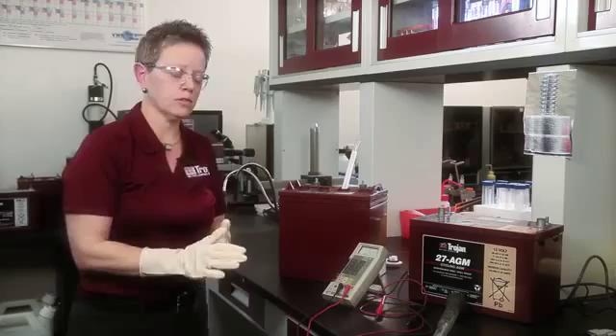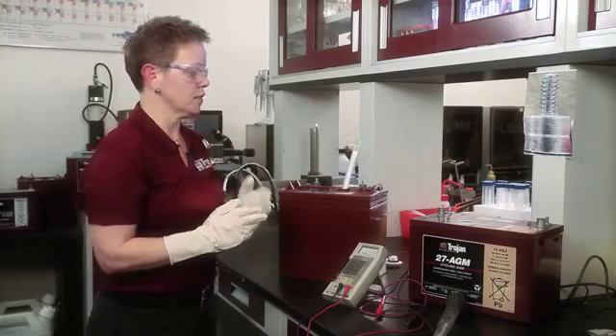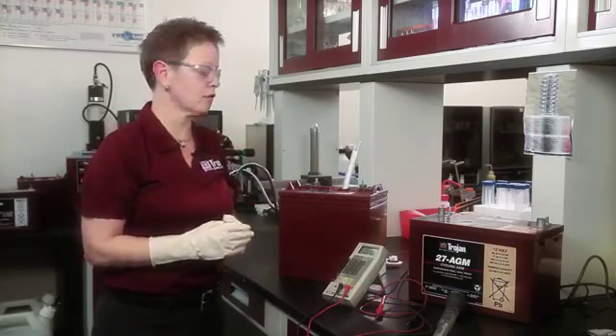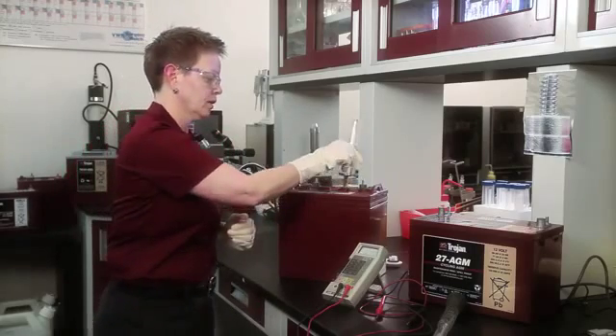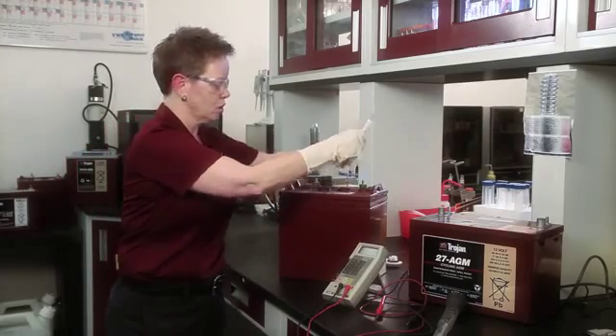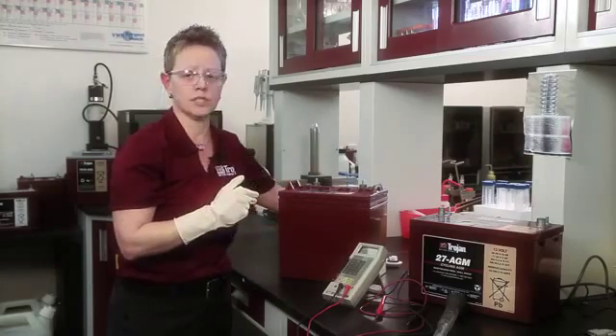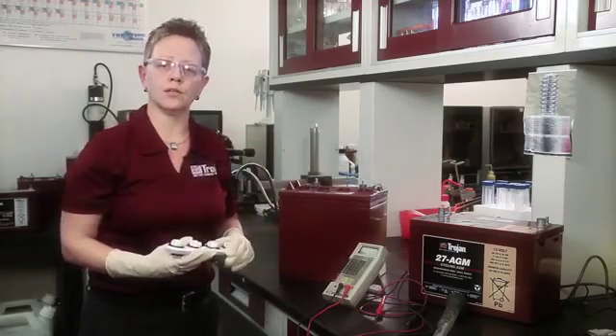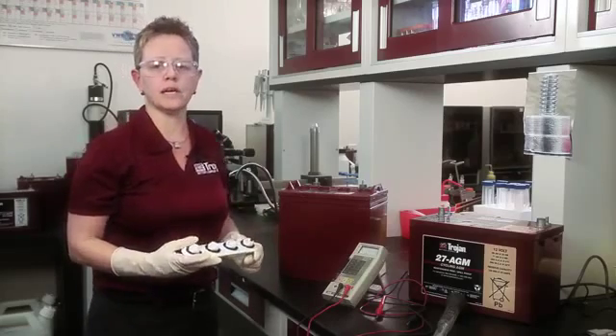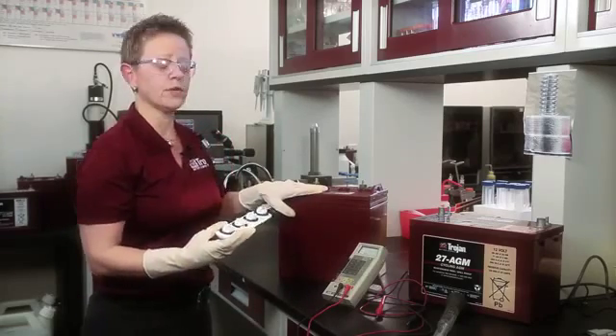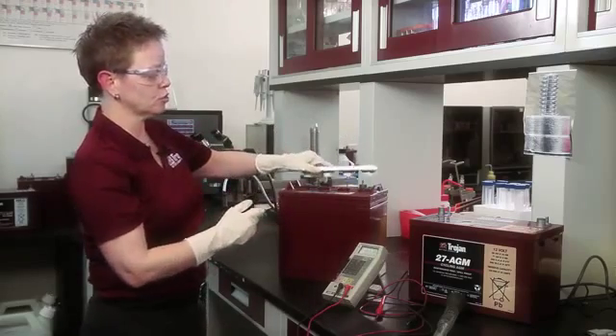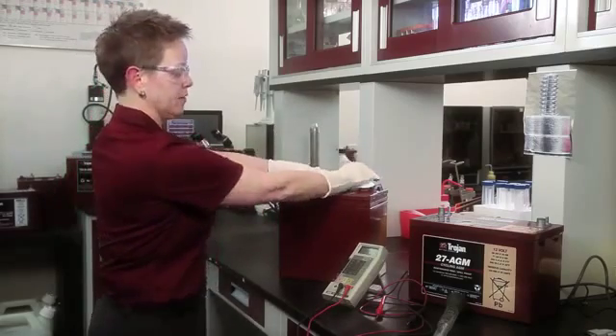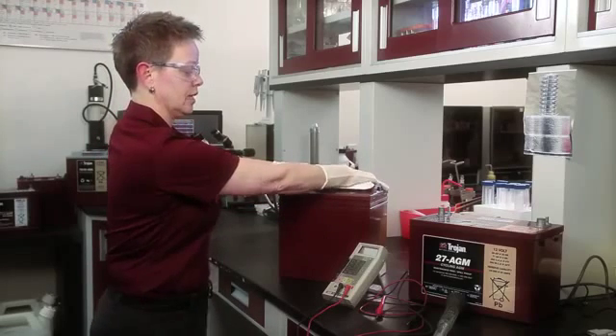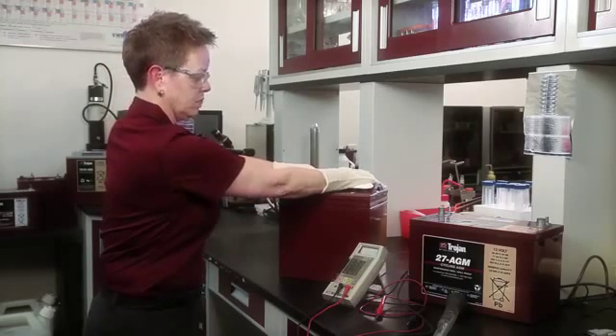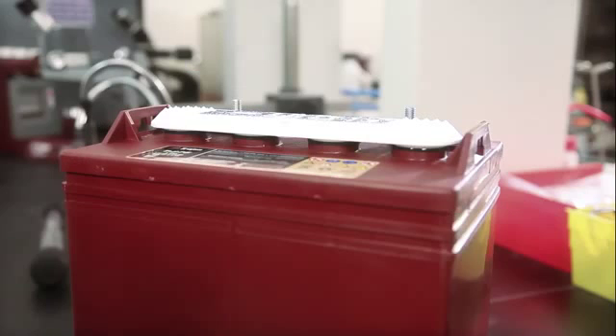You would record the values and then also record the temperature because, as I said previously, you do need to temperature correct the specific gravity. In this case, the temperature was 80 degrees, again, which is acceptable. And temperature correcting the values of specific gravity then gives you the best indicator of the state of health of your battery. Whenever you're complete, you always want to make sure that you completely reinsert the vent into the battery. Again, being careful not to get any electrolyte on you. You should have a nice snug fit, making sure all of the vent caps are completely seated.